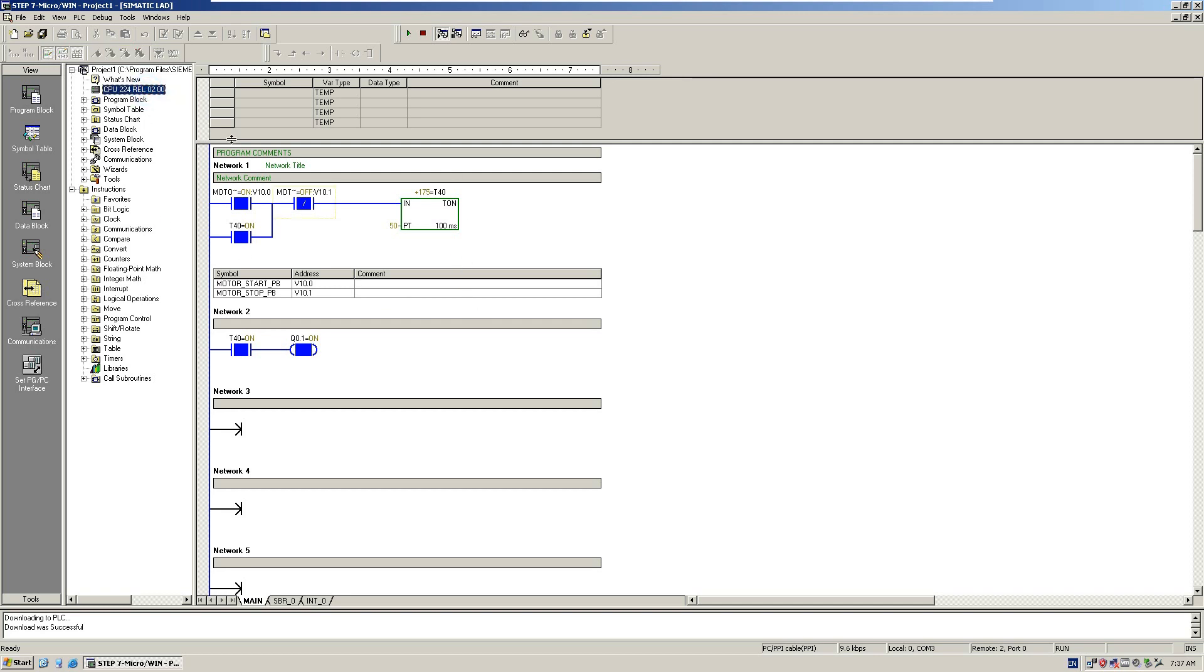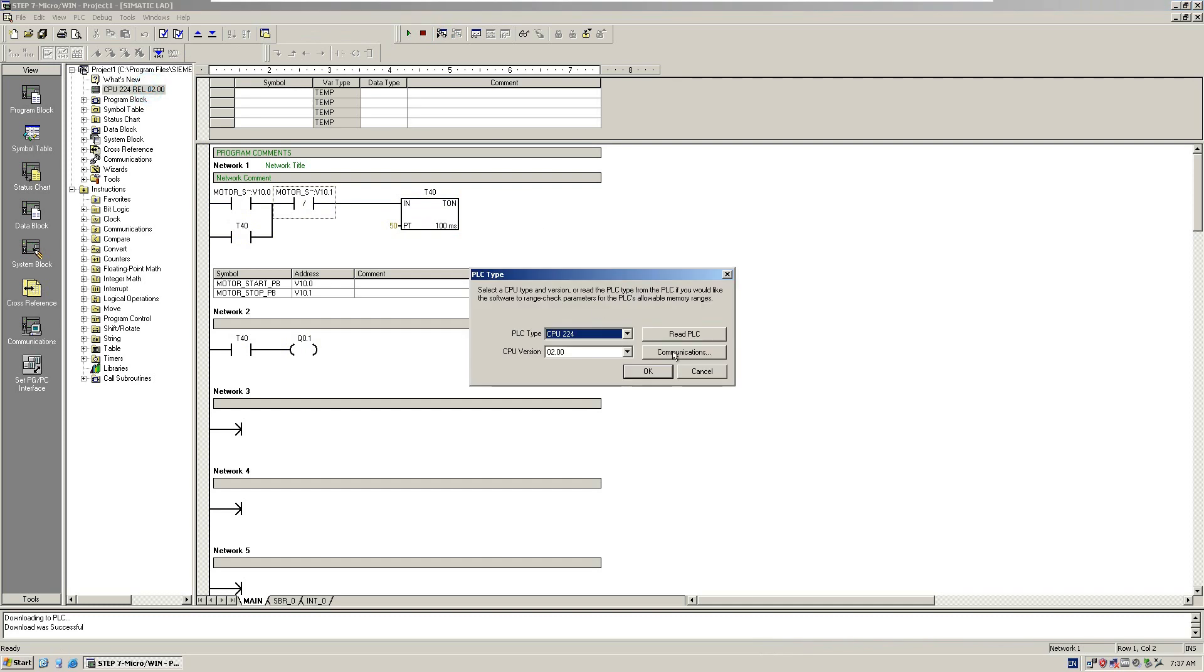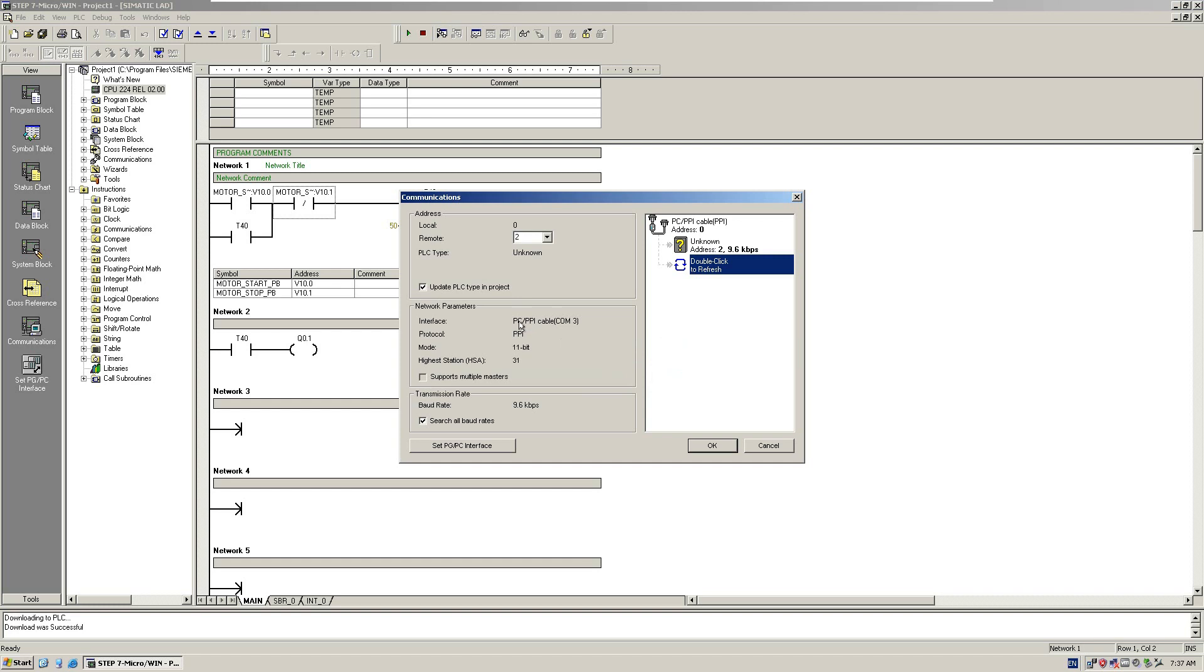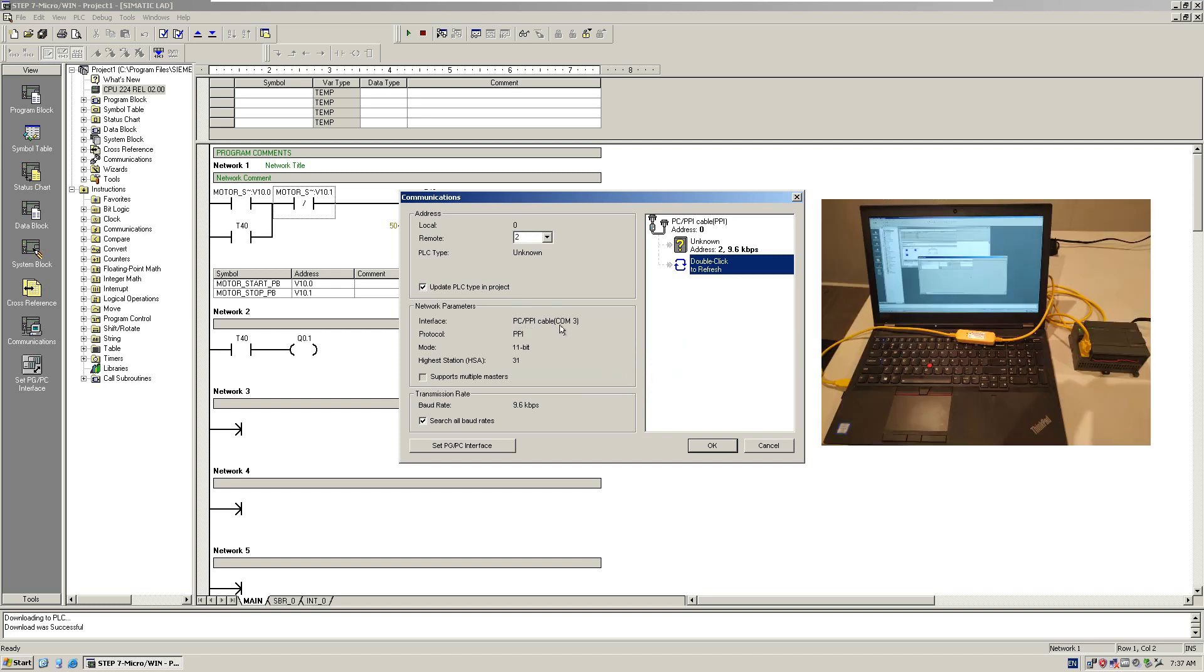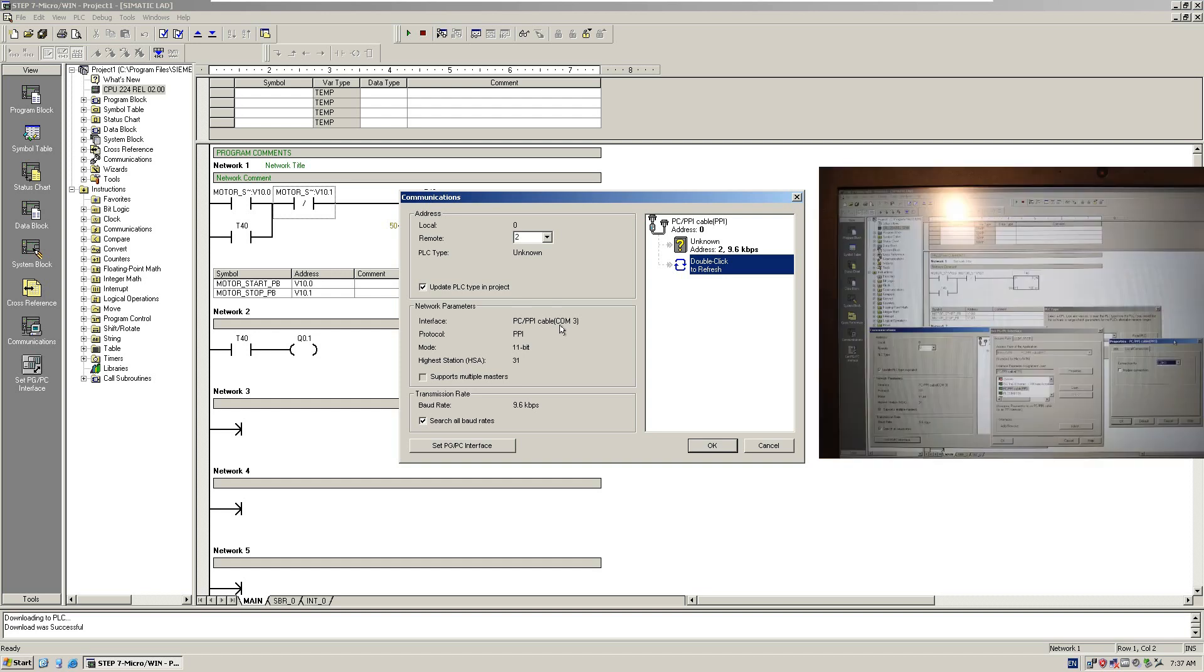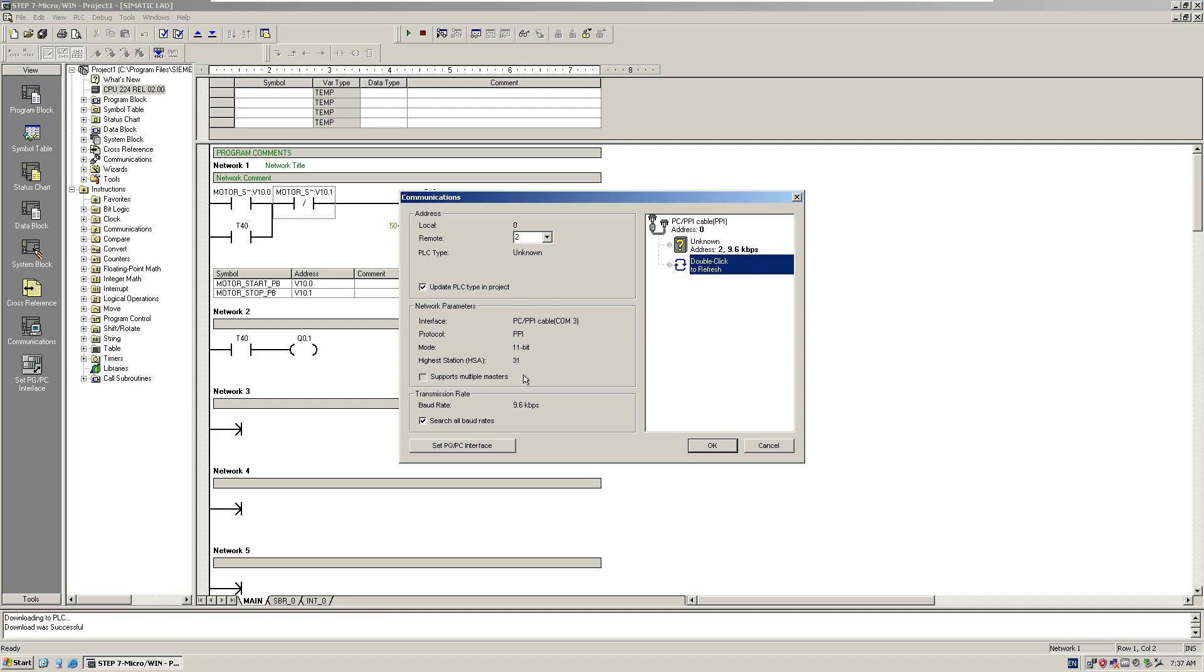Let's have a quick review. In this test, our actual setting: we select PC-PPI cable COM3. With this cable that images the USB port to a COM port in my system, that is COM3. And don't forget to select the checkbox 'search all baud rates', which allows your software to scan all transmission rates in this PPI network. That PPI network physical cable is the RS-485 cable. That is what this video wanted to show.